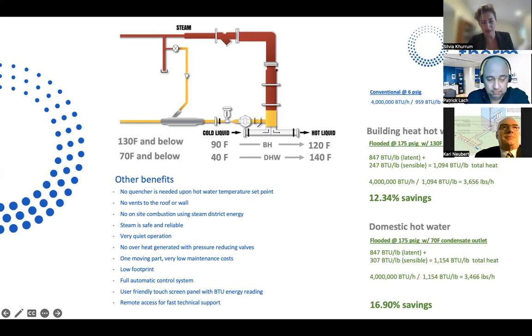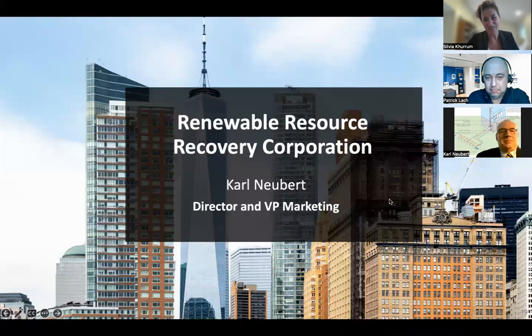And of the benefits Patrick mentioned, obviously no quenching is a cost avoidance for customers. If the condensate is too hot to dump and you need to spend energy on quenching, here is the energy recovery part. And the other unique part about Maxi-Therm is that they really deep dive into thermodynamics. They utilize a heat exchanger that is flooded to extract both latent and sensible heat. And I'll leave it at that point for all the thermodynamic fanatics like me. We know what we're talking about, but it's a great operation.